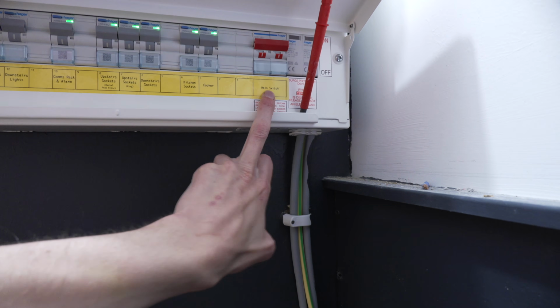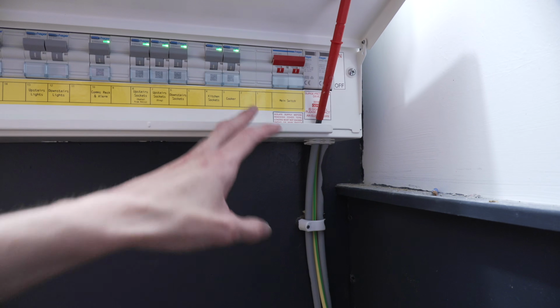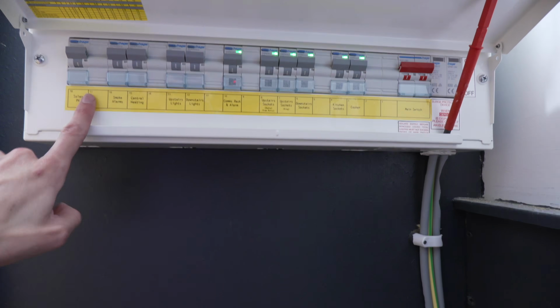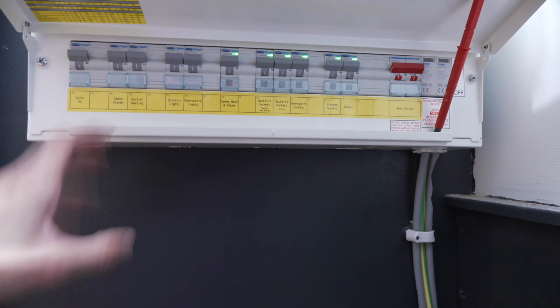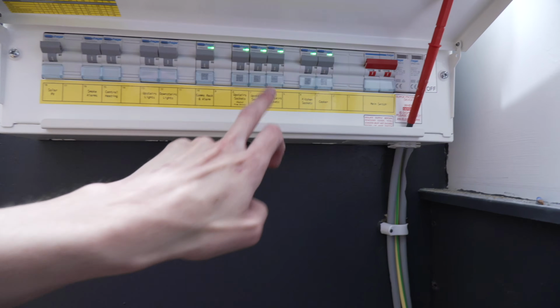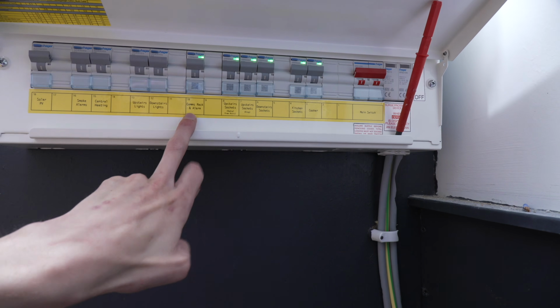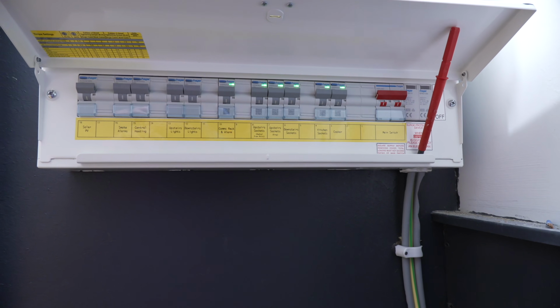Then the final CT is going to be down this end, it's going to go on the grid, so that'll be my grid connection there. That way I can monitor my consumption and export to the grid. I can monitor my solar generation, and I can get individual monitoring stats for my lighting, sockets, kitchen, and the comms rack. So yeah, that should all be good to go.